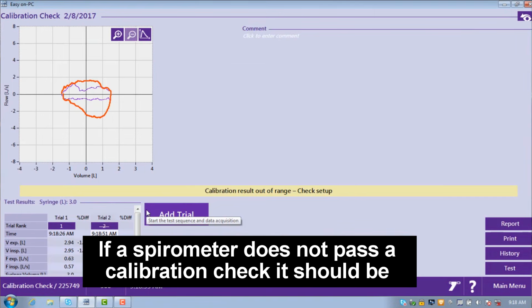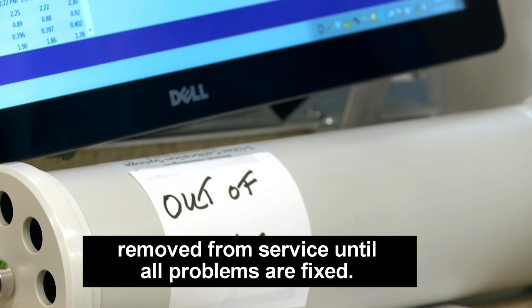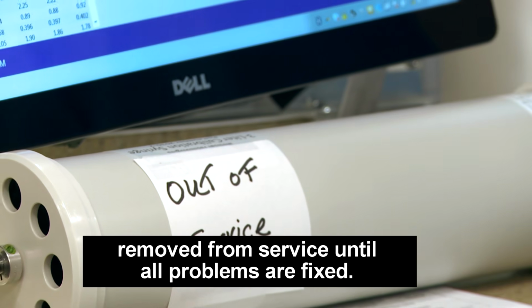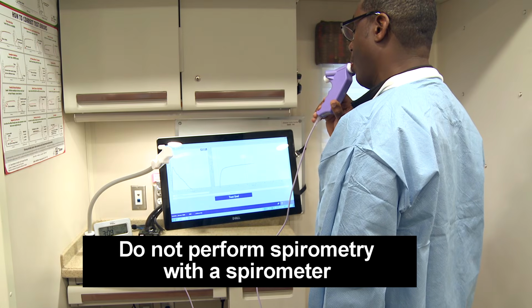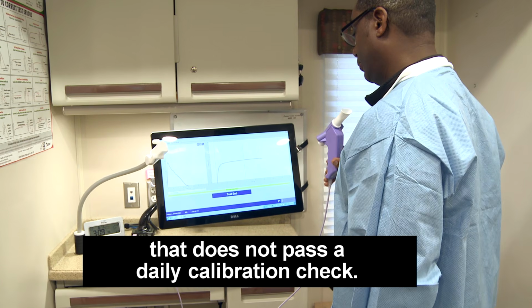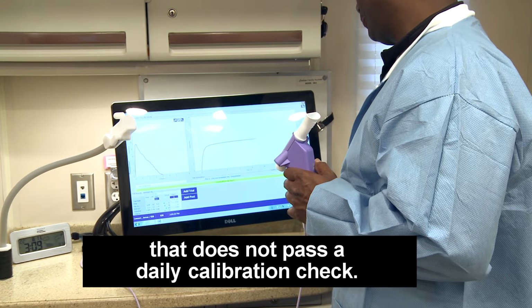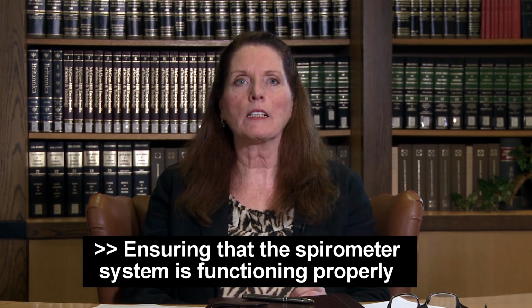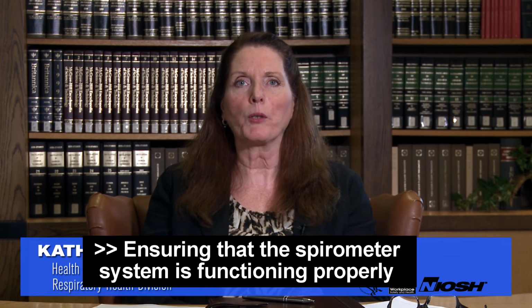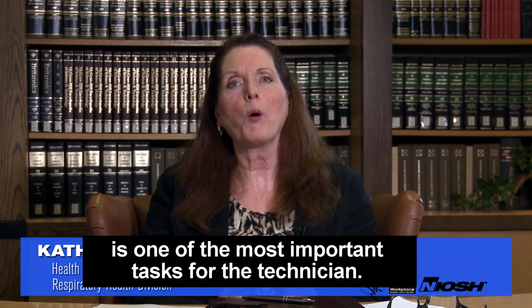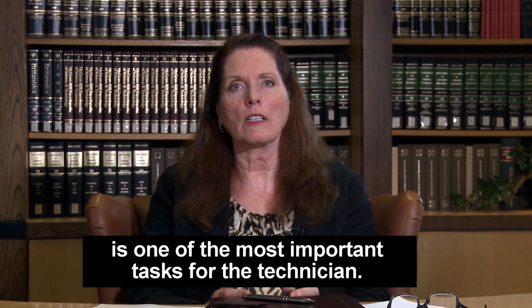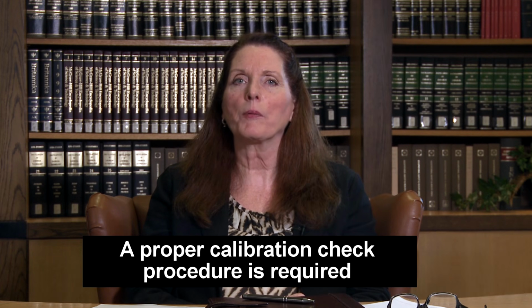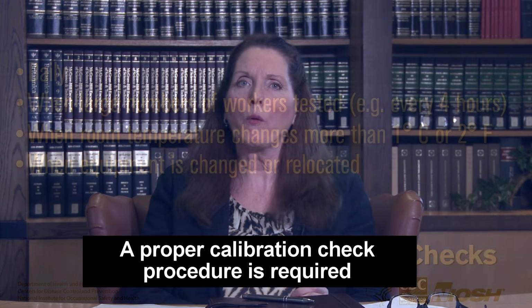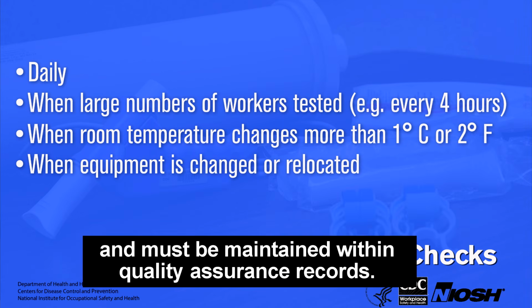If a spirometer does not pass a calibration check, it should be removed from service until all problems are fixed. Do not perform spirometry with a spirometer that does not pass a daily calibration check. Ensuring that the spirometer system is functioning properly is one of the most important tasks for the technician. A proper calibration check procedure is required and must be maintained within quality assurance records.